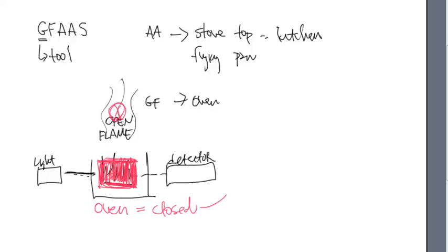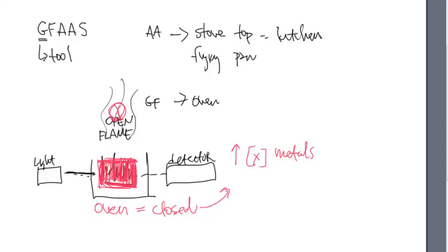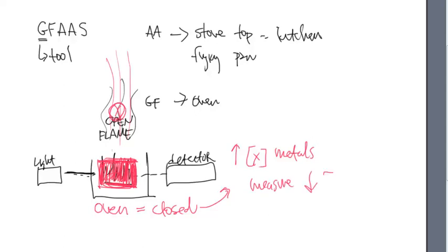And because it's closed, then that means it can increase the concentrations of the metals that you're trying to analyze for. It's not going to let them escape. In the frying pan method, or the traditional AA, this flame was open, and as soon as the metals atomize, then those atomized vapors basically can escape and get sucked out of the room. However, if I'm in a closed container and I do not allow those metals to escape and I keep them concentrated in the small area, then what this machine allows me to do...